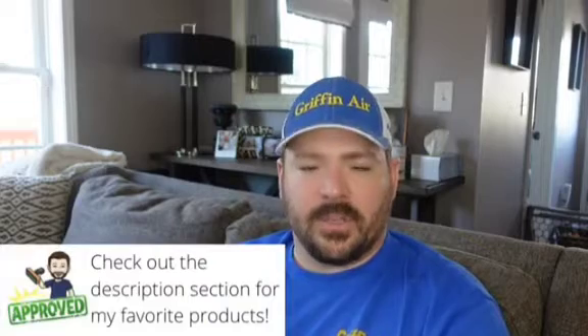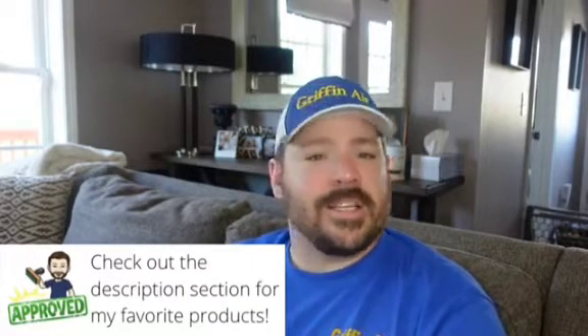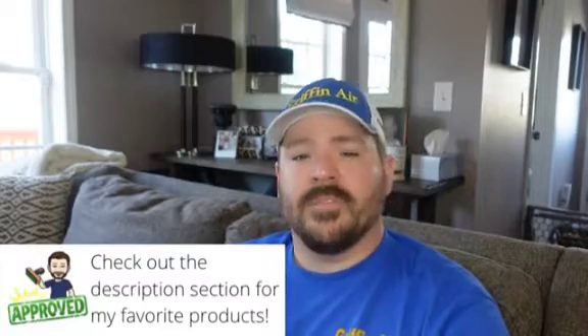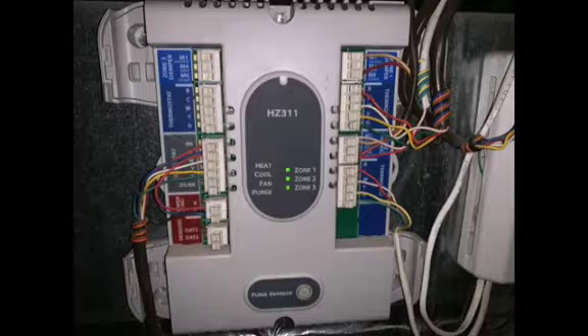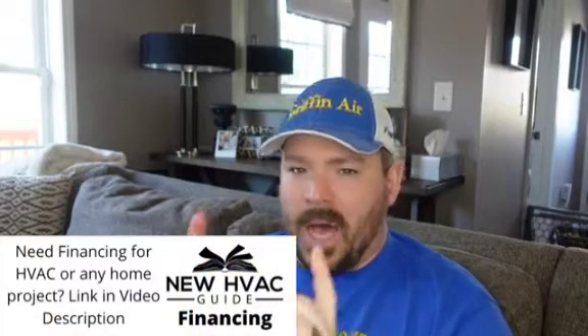But if you have a zone system, a house with multiple thermostats where each zone has a thermostat and maybe a damper or two controlling the ducts and airflow to that zone, keep in mind the thermostats are not the brains of that system. Nine times out of ten there will be some module mounted close to the indoor unit, and the thermostat sends voltage or a signal saying, this is what I'm seeing in my zone, this is what I want to happen. But ultimately that module decides what opens, what closes, what turns on.